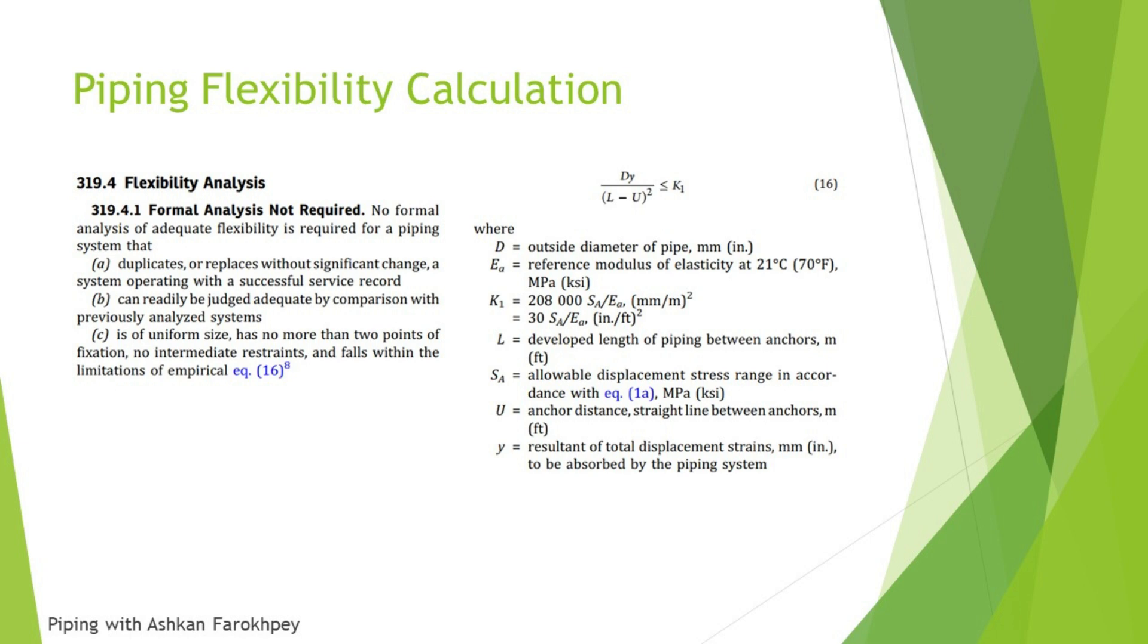In the third section, section C, it says that if your system is of uniform size and has no more than two points of fixation and no intermediate restraints exist and falls within limitations of empirical equation, you can use the formula number 16 that you can see on the right top of the page.